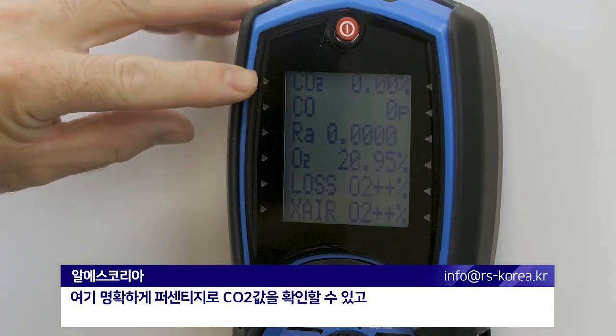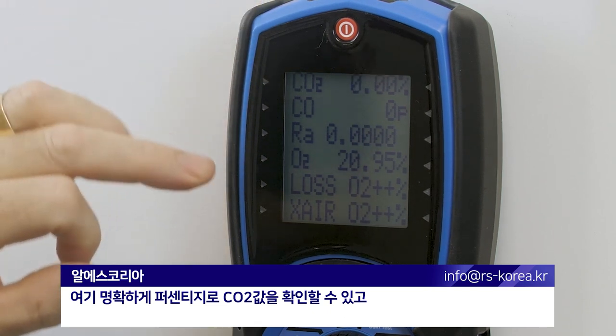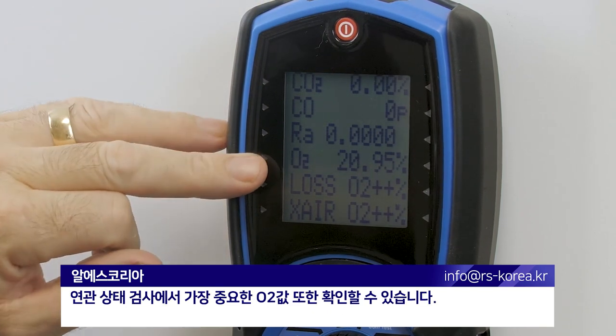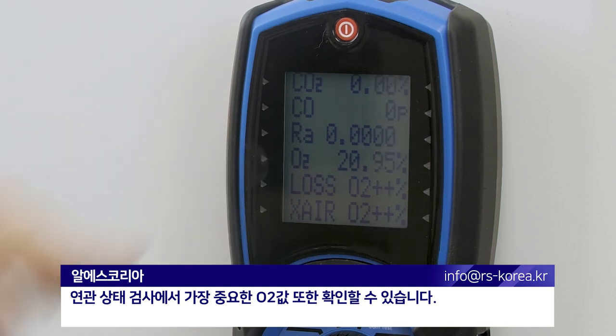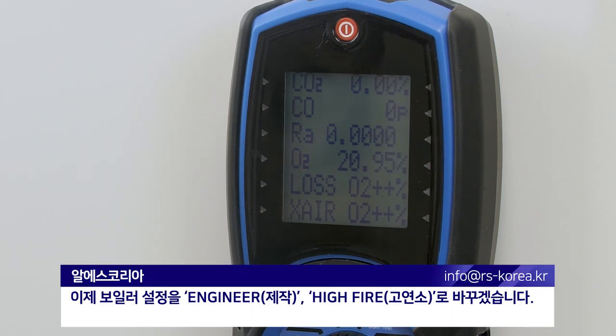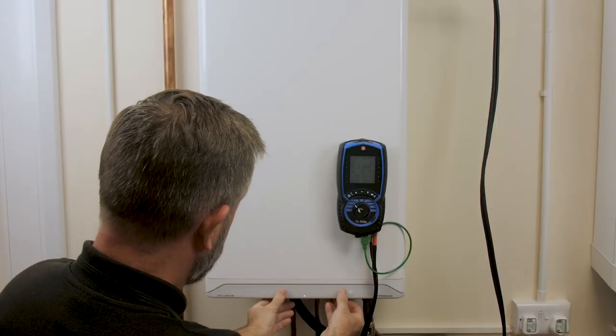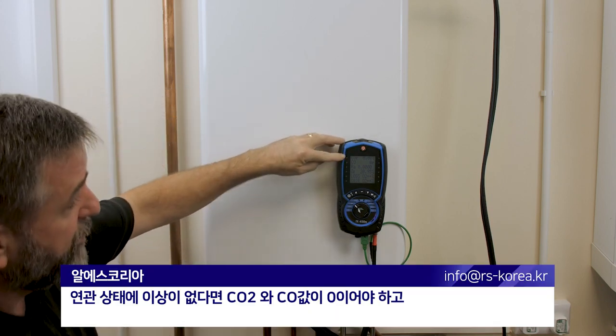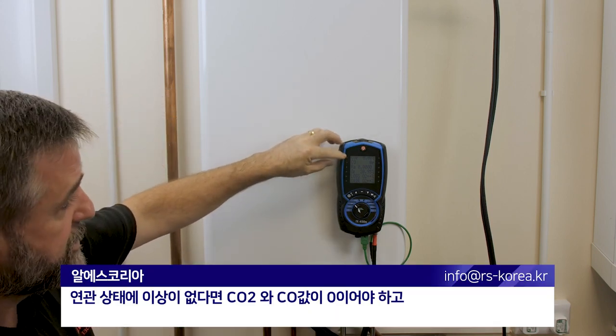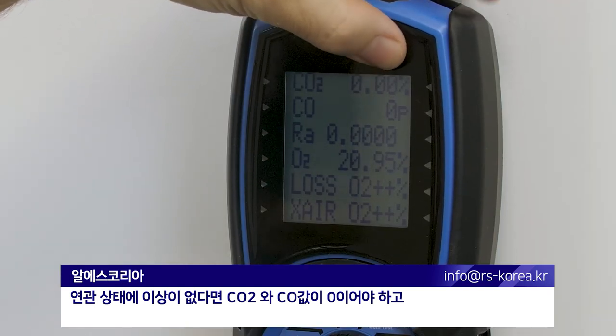On here you can see a clear indication of the CO2 as a percentage and also the O2, which we're most interested in for flue integrity checking. I'll put the boiler now into engineer mode on high fire. What we're looking for — if flue integrity is good — we should maintain zeros on CO2 and CO.